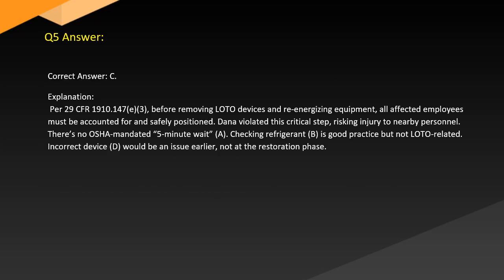Answer. Correct answer: C. Explanation. Per 29 CFR 1910.147(e)(3), before removing LOTO devices and re-energizing equipment, all affected employees must be accounted for and safely positioned. Dana violated this critical step, risking injury to nearby personnel. There's no OSHA-mandated 5-minute wait. A. Checking refrigerant. B. Is good practice but not LOTO related. Incorrect device would be an issue earlier, not at the restoration phase.